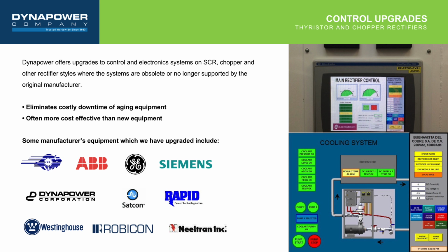The cost to replace that equipment is an order of several millions of dollars in value, as well as months of lost production. Upgrading an existing aging high-power rectifier system with the latest digital controls is a cost-effective alternative to full system replacement or costly maintenance. A Dynapower control upgrade can significantly extend the operating life of an existing high-power rectifier system and provide improved performance, safety, and reliability. High-power rectifier control platforms are designed with specialized electronics that, due to rapid technology advances, can quickly become obsolete, whereas rectifier transformers can last decades.